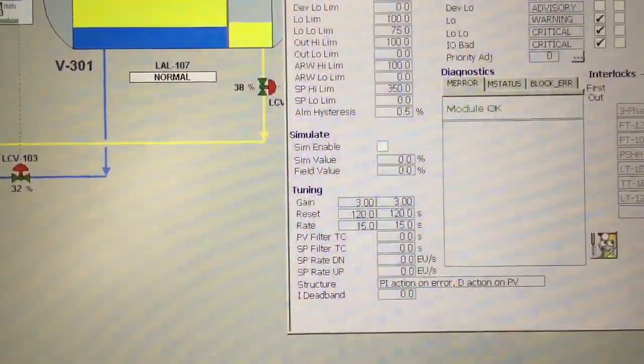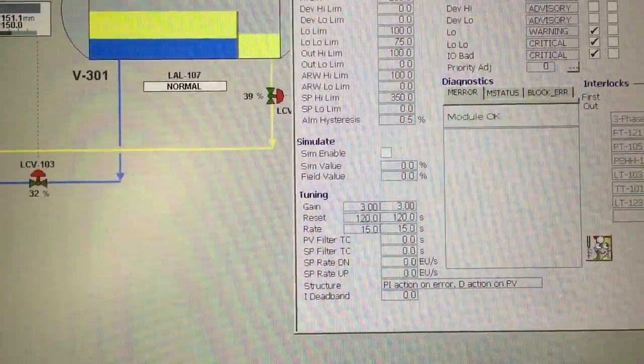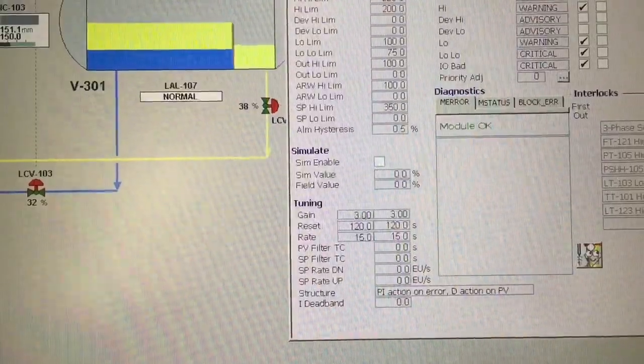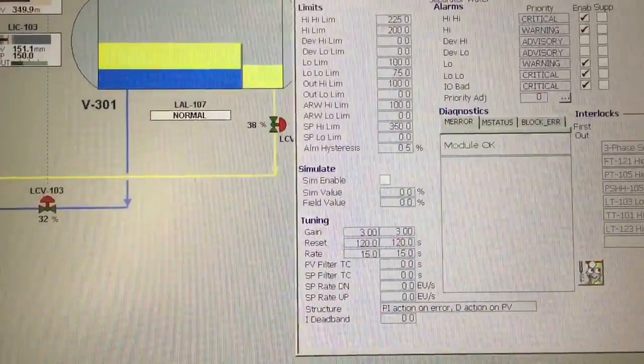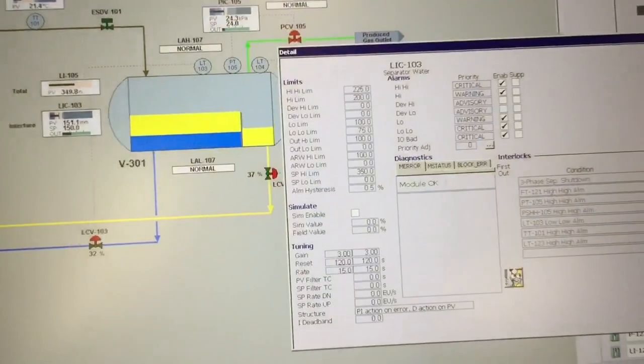We have our gain at 3, our reset at 120 seconds, and our rate set for 15 seconds. It's a pretty slow process so we're using rate or derivative as well.